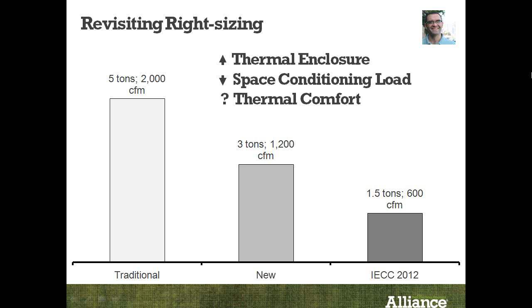When you were delivering 2,000 CFM of air, you had a lot of air blowing into a room, and you had good turnover in the room and good mixing because you had such a large volume of air. Now there isn't as much air going into the room, so you may not get the mixing you need. What this means is you're basically oversized, or the system you're installing is going to be larger than what you need.